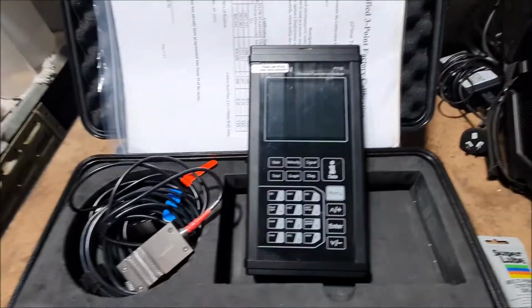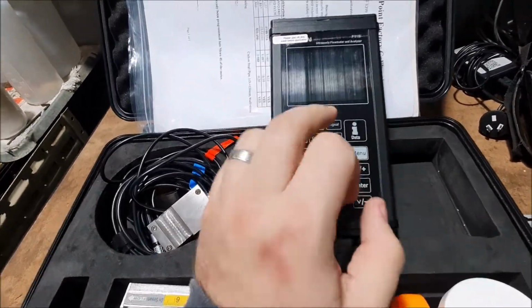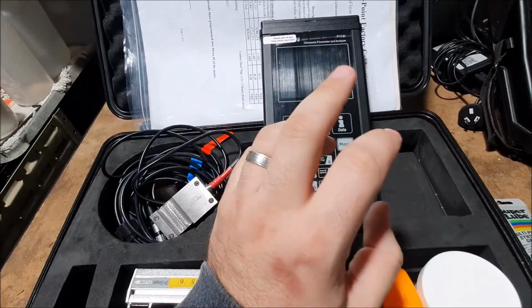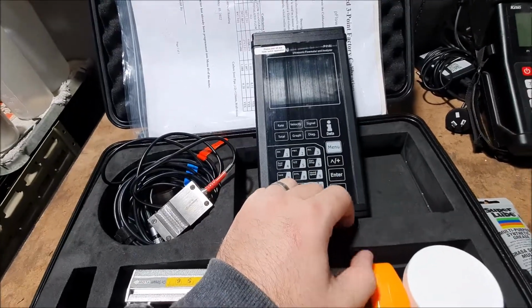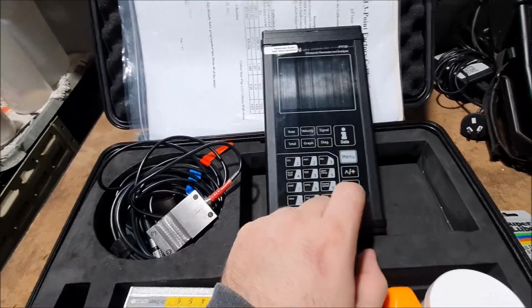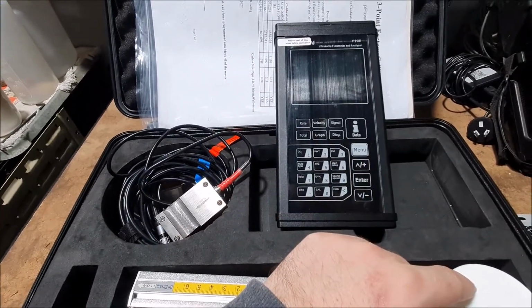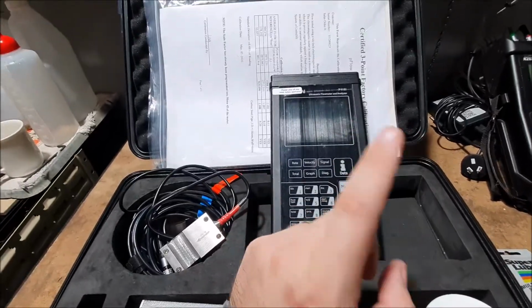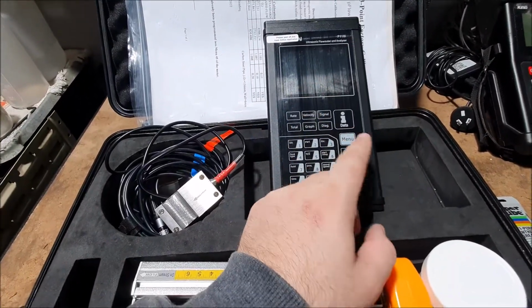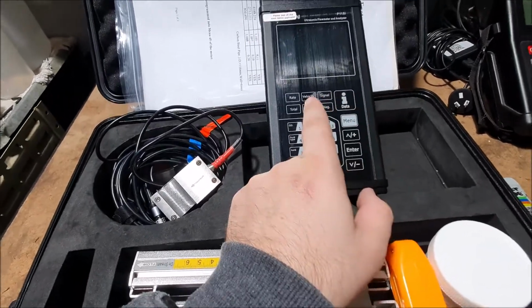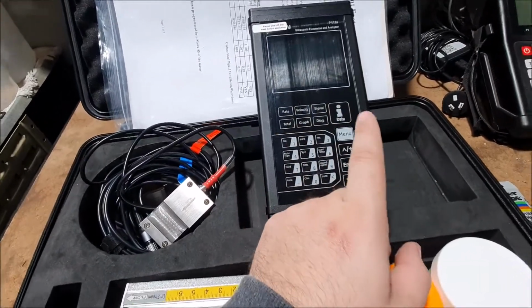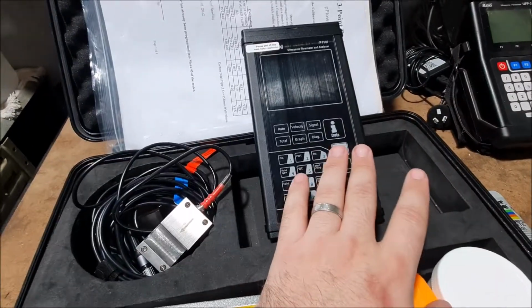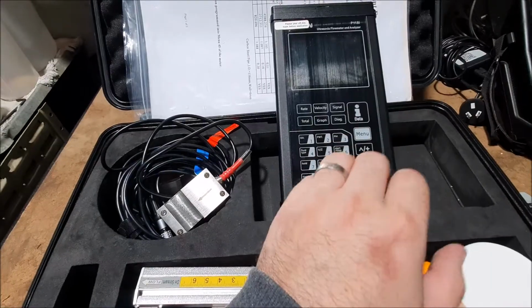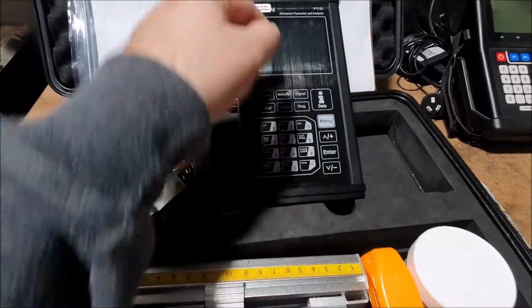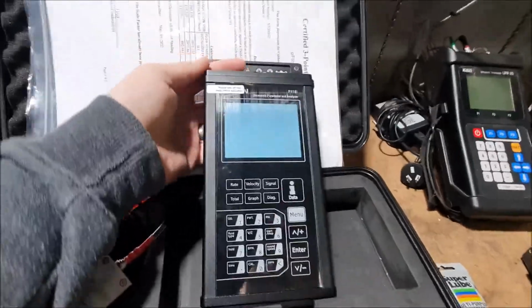Okay, now there's a couple advantages of the P118 over the P117. So that'll be that this is a better technology. It's PicoFly technology, which offers increased accuracy. So it'll be 0.5% accuracy rather than the 1% of the P117. It can work with higher velocities, so that's up to 12 meters per second velocities on this model. It has better repeatability at 0.15%. It can work on larger pipes, so this will work on pipes from DN15 to 6000, and also it's color rather than just black and white on the display.